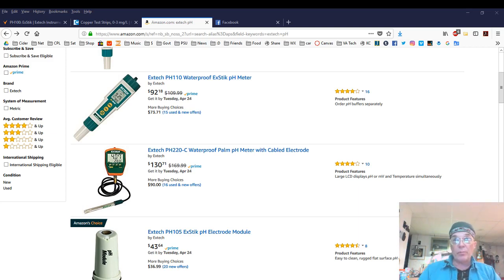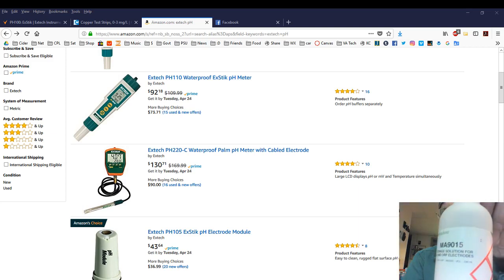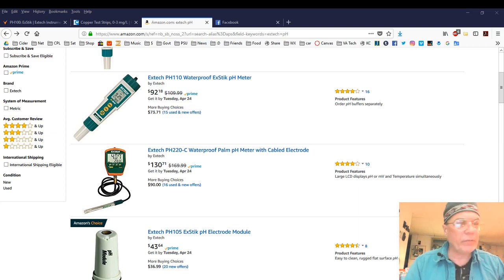Even if you buy a disposable pH meter, I don't say disposable, a low-cost pocket one, you want to use storage solution. They're supposed to come with a little sponge in the cap that you can soak with the storage solution to keep you from getting a dry bulb. If you don't have one, make one. Cut a little piece of sponge, push it in there, wet it thoroughly with storage solution. Keep your pH probes wet, or they will fail you sooner than they should have, could have.